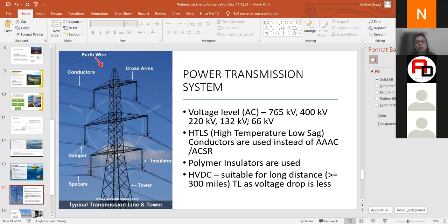This is the conductor also. That's an HTLS conductor, nowadays introduced because it is a high temperature, low sag conductor. When transmitting over long distance, this kind of HTLS conductor is used because of the low sag. If we save on sag, we can reduce the number of towers, which reduces the cost. Also, constructing a transmission tower consumes land, and land is a very big problem in our country, especially in our state. So this HTLS conductor has been introduced.